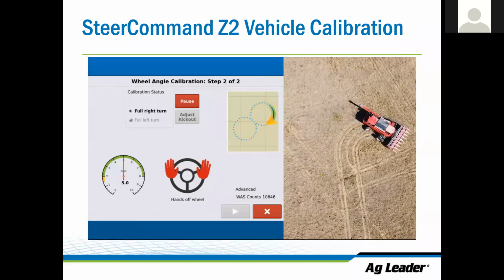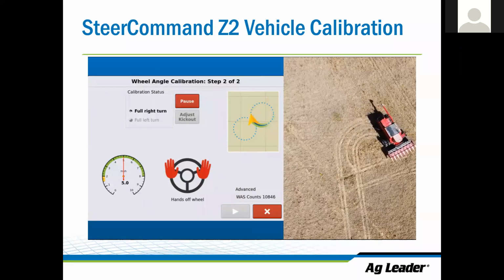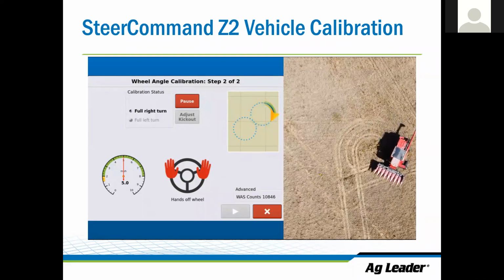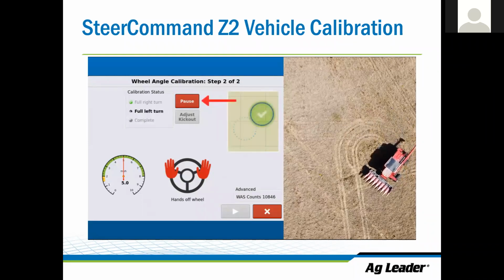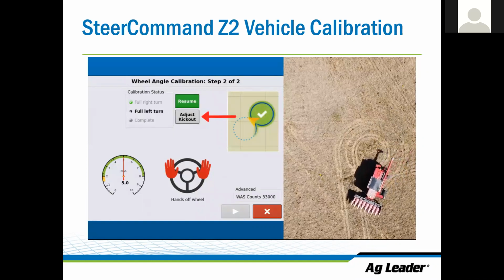If the automated turn sequence is unintentionally disengaged repeatedly by the kickout sensor, that means the kickout set point is likely too sensitive. To adjust, pause the calibration, then tap Adjust Kickout.